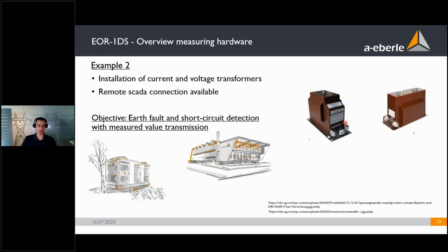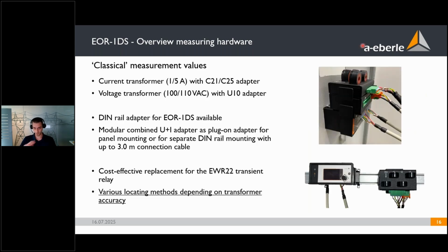Example number 2 would be that you do have current and voltage transformers installed, or you're able to install them, and you do have a remote SCADA connection. Your objective in this case would be to have earth fault and short circuit detection with measured value transmission. For this option, we offer additional adapters for the classical measurement values. As you can see here in these 2 pictures, there is a current transformer for 1 or 5 amps nominal current with the C21 or C25 adapter. The only difference between these 2 is that one measures all the phase currents and the zero sequence current, and the other one measures only the zero sequence current.